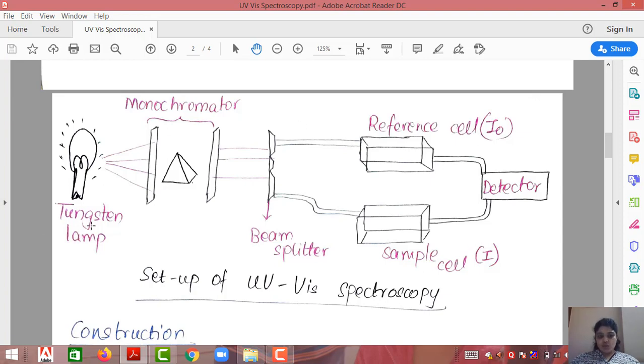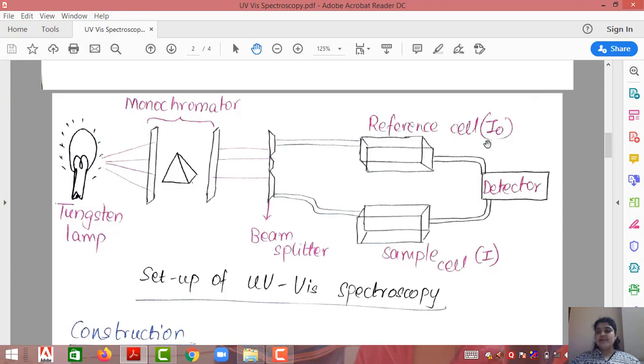The tungsten lamp is the light source whose wavelength and energy are known. The monochromator converts the light into a parallel beam. The beam splitter converts it into two different light sources. The reference is the one whose intensity is known, the sample is the one whose intensity is to be found out, and the detector compares these two intensities. This basic setup is known as the spectrophotometer.